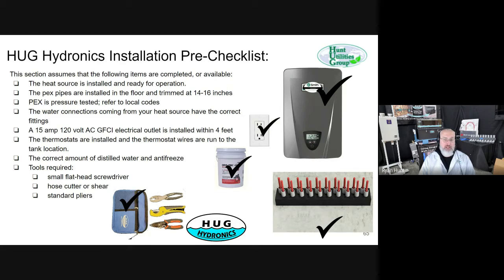So make sure your boiler's on the wall. Make sure you have an outlet. If you're running a smart thermostat, we'll send a 24-volt power supply with you. That also needs a plug. A gas water heater will need a plug, so you might need 3 nearby. And you make sure you get your loops in the floor. You know which end is which and which loop goes where. Antifreeze if you need it, and then make sure you got the tools that you need to install it: pliers, a tubing cutter, a wire cutter, and a tiny screwdriver.